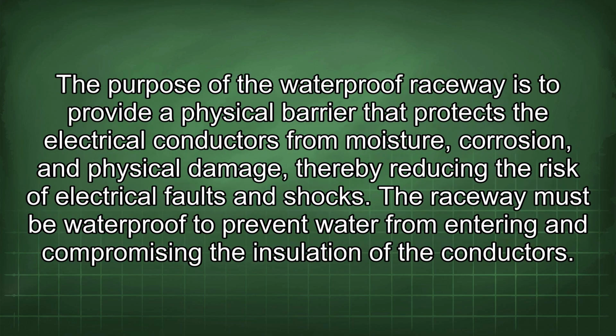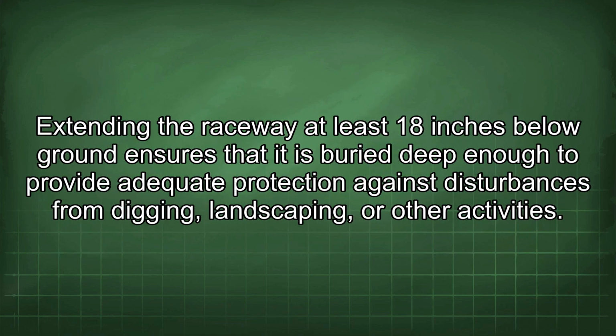The purpose of the waterproof raceway is to provide a physical barrier that protects the electrical conductors from moisture, corrosion, and physical damage, thereby reducing the risk of electrical faults and shocks. The raceway must be waterproof to prevent water from entering and compromising the insulation of the conductors. Extending the raceway at least 18 inches below ground ensures that it is buried deep enough to provide adequate protection against disturbances from digging, landscaping, or other activities.